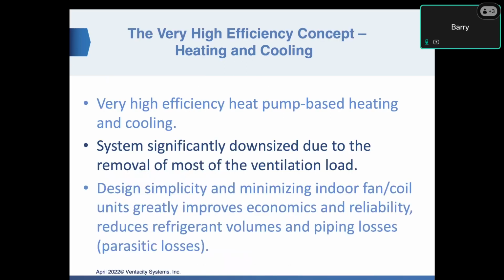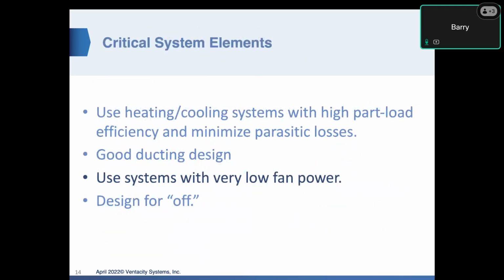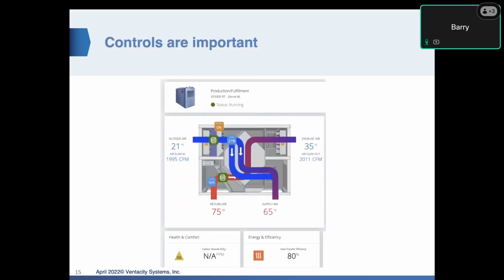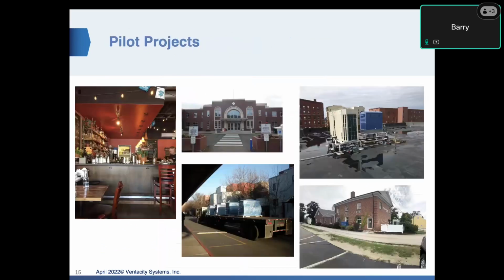So again, we're system downsized, with very low fan power, heat pumps, and ventilation systems that use very low fan power reduce a lot of energy. And then controls with demand control, scheduling, and other things are very important to the whole system. And the key here is you can do this with almost any type of building.